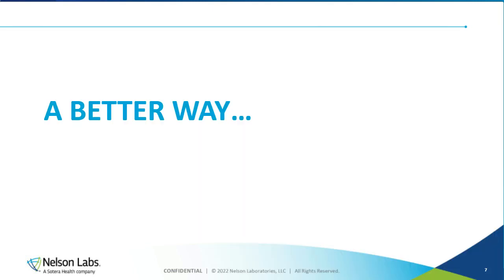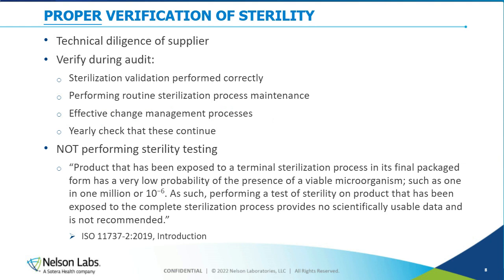So the better way to properly verify sterility, first, is the technical diligence of your supplier, or your supplier audits. You need to have someone either there during the audit or as a resource to verify that at least these 4 items are in place: that the initial validation is performed correctly, and that they're performing the routine sterilization process maintenance. So every form of sterilization has some type of routine maintenance that should be performed that involves testing. And that's always the case, whether it's a steam or gas option or radiation.